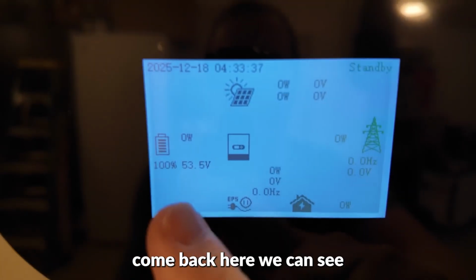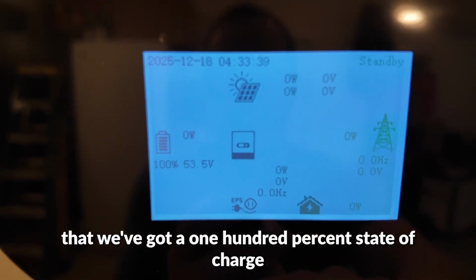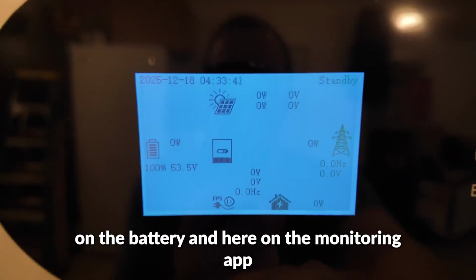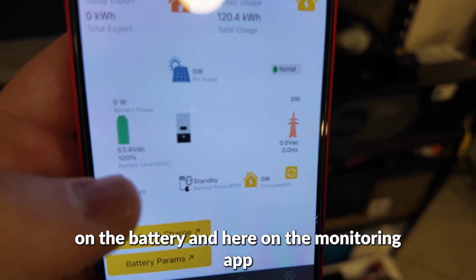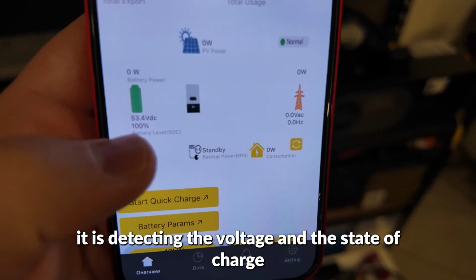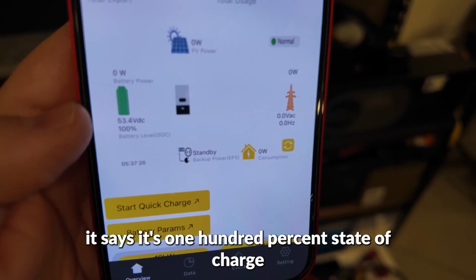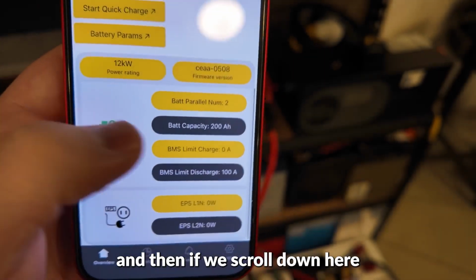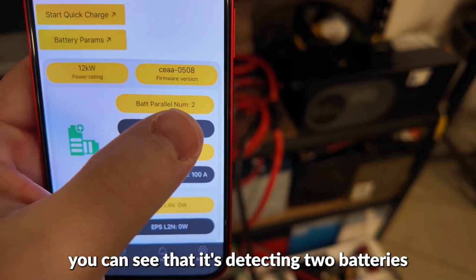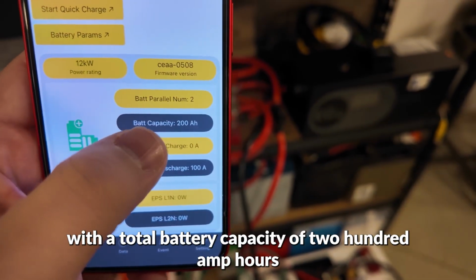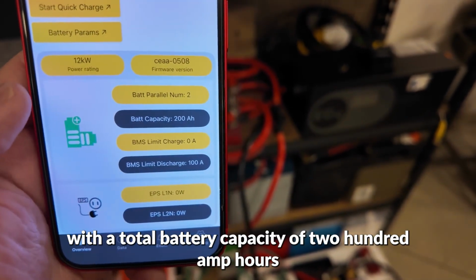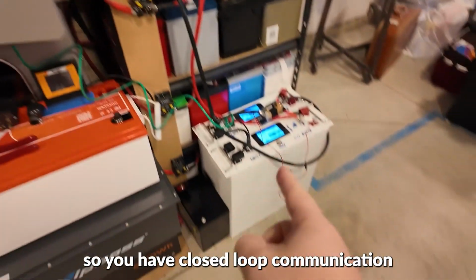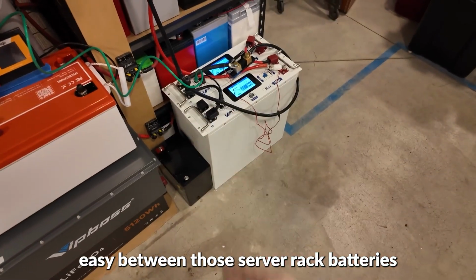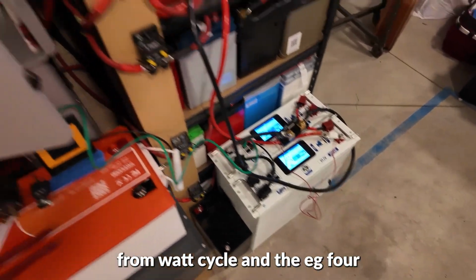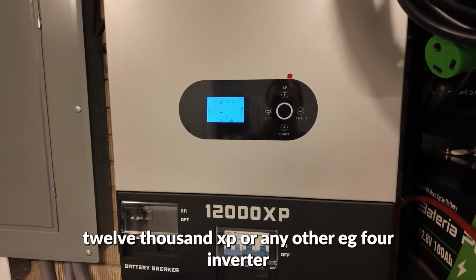Back here we can see we've got a 100% state of charge on the battery. On the monitoring app, it's detecting the voltage and state of charge, and it says 100% state of charge. If we scroll down, it's detecting 2 batteries in parallel with a total battery capacity of 200 amp hours. So you have easy closed loop communication between these server rack batteries from WattCycle and the EG4 12000 XP, or any other EG4 inverter.